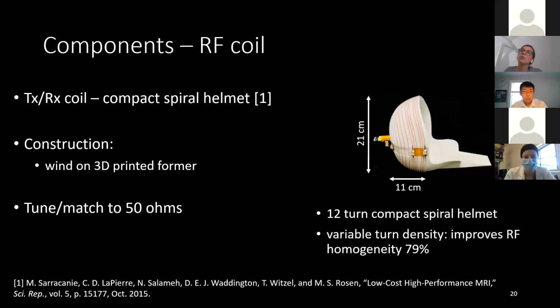Okay, so another important component is the RF coil. This is the coil that does the RF excitation and also measures the MR signal. We use a transmit receive coil, so we use a single compact spiral helmet coil to do both the transmit and the receive. And this is the design that our community has found to work pretty well in these low field systems.